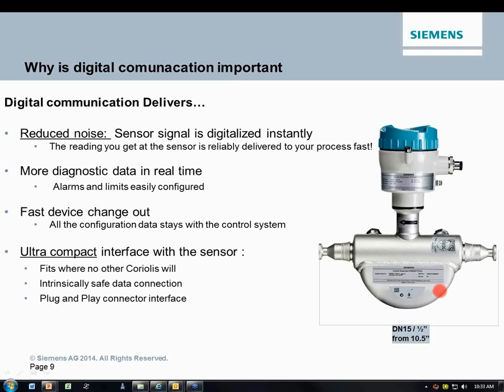Since the Coriolis meter uses smaller tubes, is there pressure drop data available for specific fluids? Absolutely. It's not a table. It's actually a program that you can get from the representative who's hosting this particular thing. What you would do is input the viscosity of the flow that you have, and the flow rate that you have. It's always nice to have the temperature and the density as well. You put all that data in, and you can change the tube size and see how it affects the pressure drop. We don't even need to know what you're flowing. Just put in the viscosity data. That's all the questions we have for now.